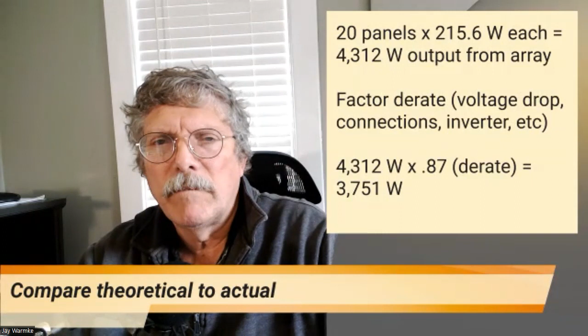So there are going to be some other losses. You're going to have to factor that in when you design your system. In this example, we estimated 87% or 13% loss from the DC array to the AC output. That may be a little bit high in today's market if you're using optimizers or microinverters. When I design a system anymore, I usually plug in 10% just to be safe. Anyway, so we take our 4,312 watts from the array, multiply it times 0.87, and we find that this array should be producing 3,751 watts at that moment.